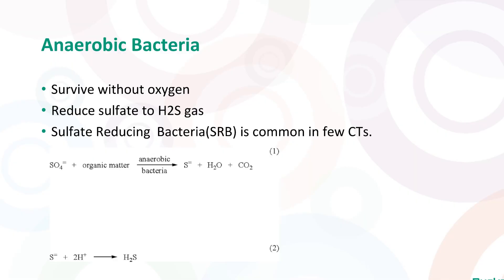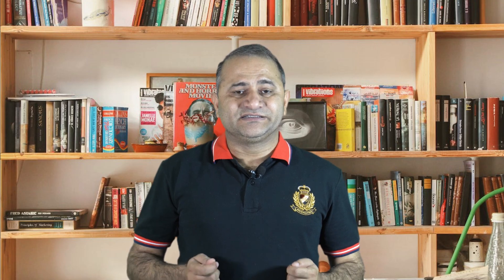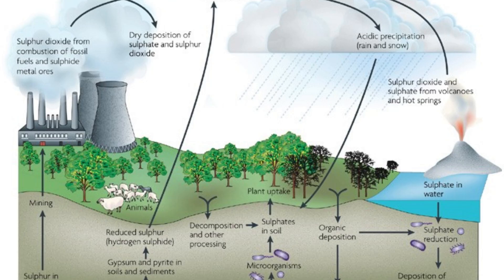The second type of bacteria are anaerobic bacteria. These bacteria cannot survive with oxygen, so usually they grow under deposits. We can see these bacteria in heat exchangers where mud deposits are present. Sulfate-reducing bacteria is a famous anaerobic bacterium. We obtain sulfur in all our fossil fuels because of sulfate-reducing bacteria.